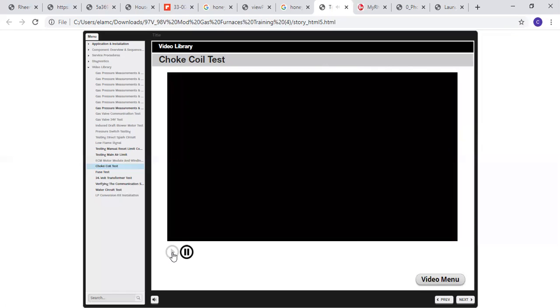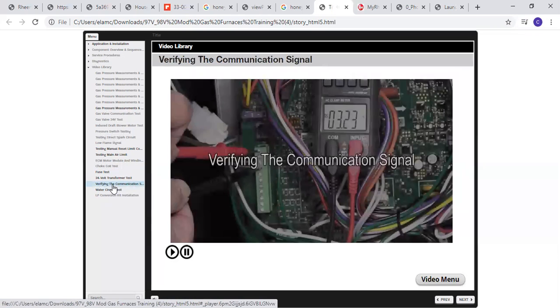So that's a pretty easy test. It's easy to identify. Like I said, if you have your 120 volts to the motor, then you know your choke is good. Okay, we'll get into this. Here's a big one. If you're verifying the communication signal, with other brands, they kept that kind of secret for years as far as what the communication voltage was. This video here will actually show you how to verify the communication signal from the board.